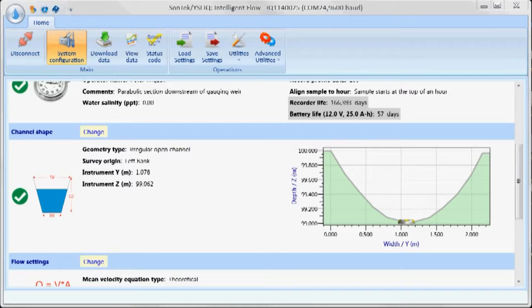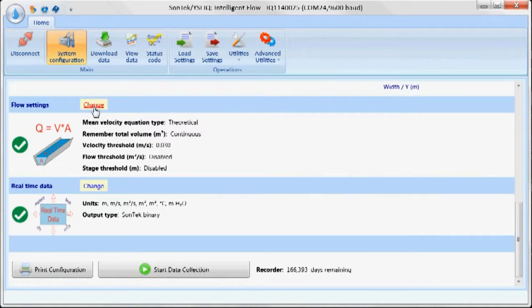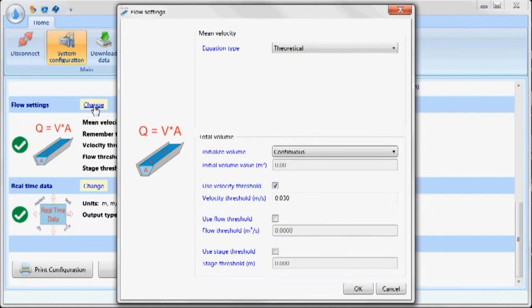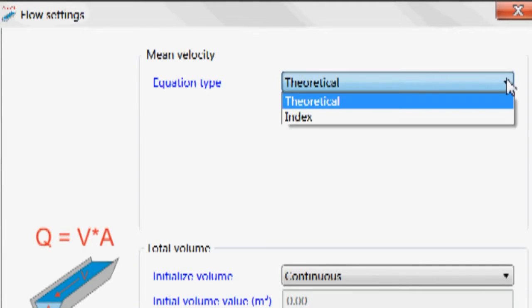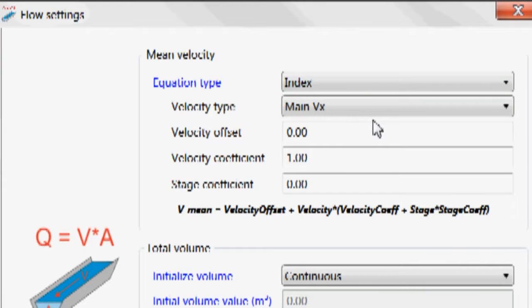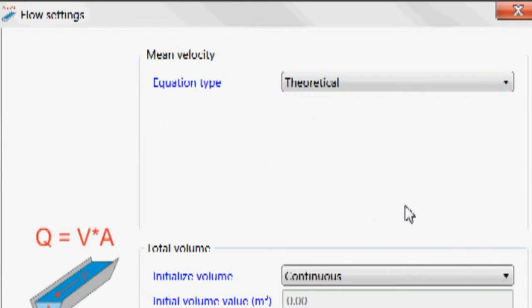Now the next thing is I have to tell it how I am going to calculate flow. I basically have two options: a theoretical calculation, or a velocity index calibration. This discussion is rather lengthy, but the theoretical setting is what I want to use if I want the IQ to automatically calculate flow. If I want to provide my own equation to calculate flow, I can click index, select my velocity type, and put in my velocity index equation. In most cases, especially in irrigation canals, you're going to simply select theoretical, and you'll be done.